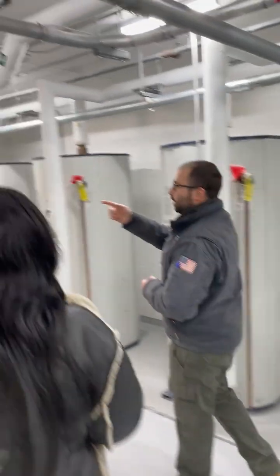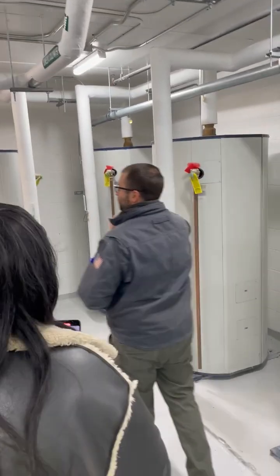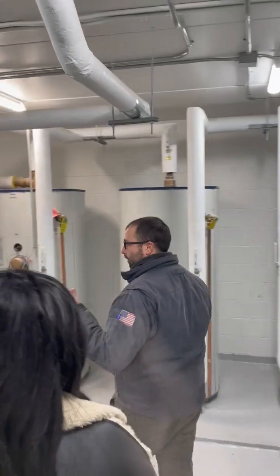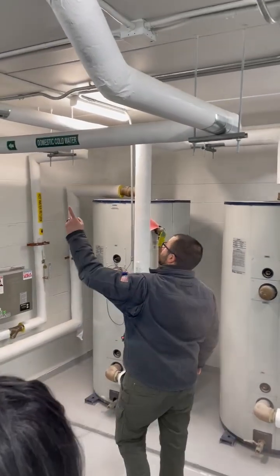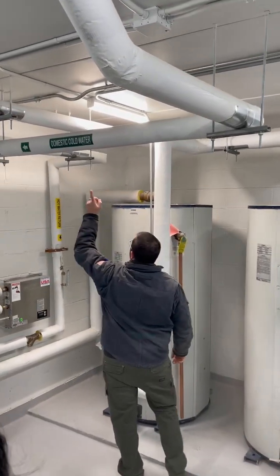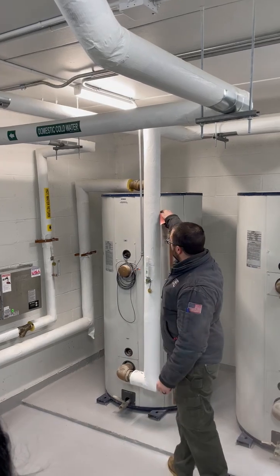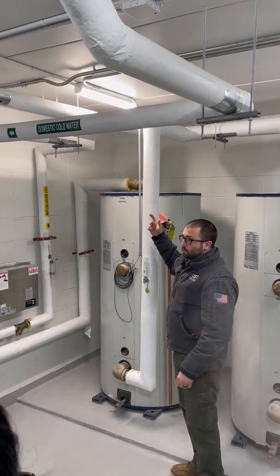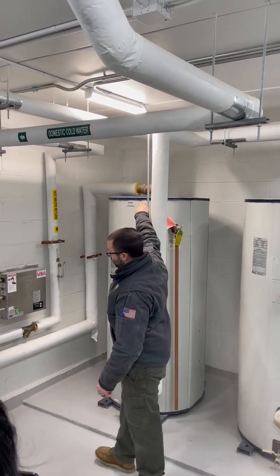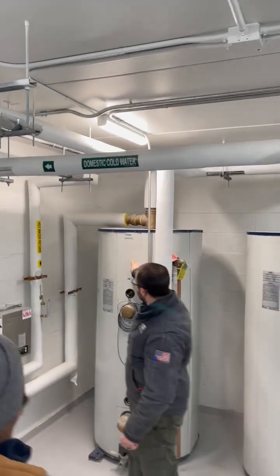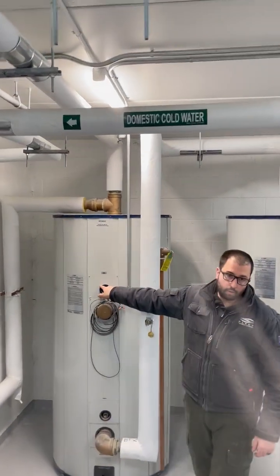Okay? So if I pull 180 degrees from my CO2 heat pumps, 170 to the heat exchangers, there's 170 degrees in this line right here. 170 degrees is going to be going into this tank through what's called an injection tee. You see that there's 2 lines coming across the top. So the injection tee is going to be forcing water into this tank.